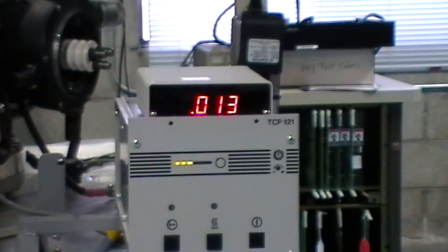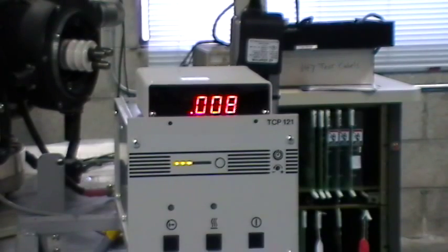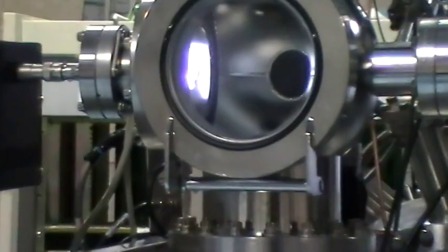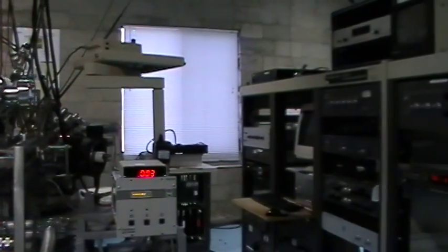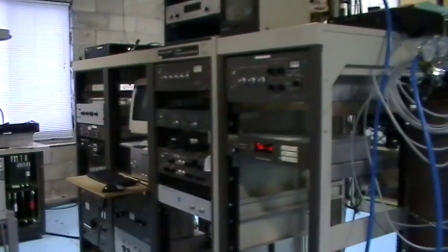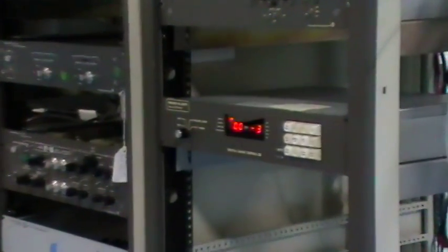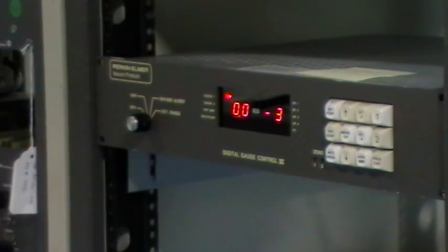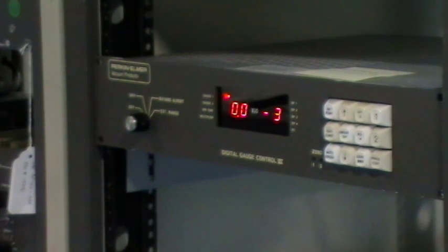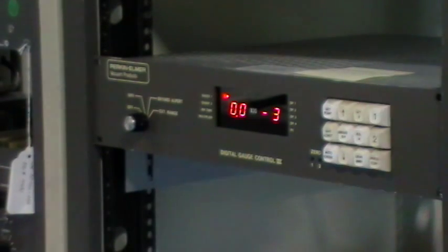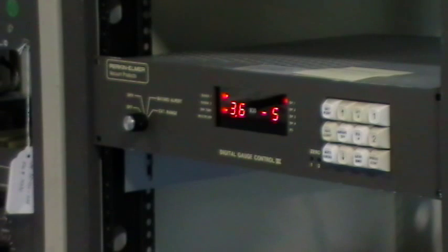Vacuum starting to come down. Okay, here the lamp is increasing in brightness. Okay, now that we've been pumping for a few minutes, if our TC gauge indicated that we're down in the minus 3 range or lower, it's safe to turn on the ion gauge. All right, the pressure's coming up a little bit from the ion gauge turning on. We're getting a little degassing, and then that will start pumping back down.